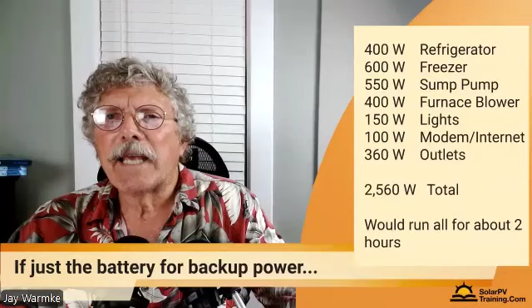Well, we do a load analysis. In this case, these are the loads I want to back up. It amounts to 2560 watts. That's less than my 3840, so I'm good there. It's going to run about 2 hours—2500 watts, 5 kilowatt hours of load. If I were just running off my battery, that's where I'm at, running all these loads at night with no array, about 2 hours.